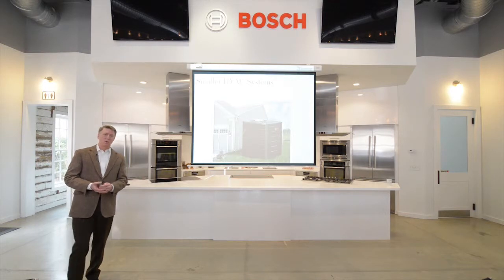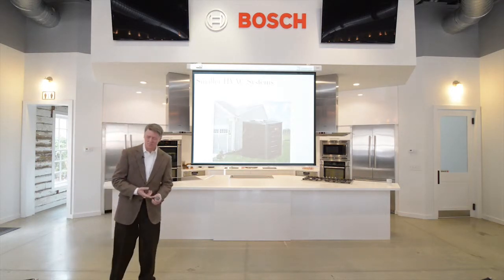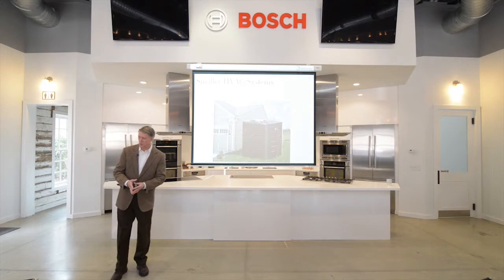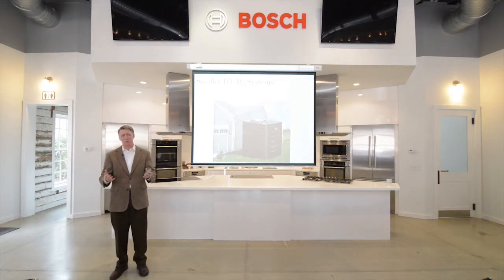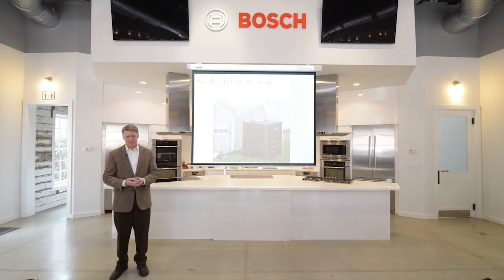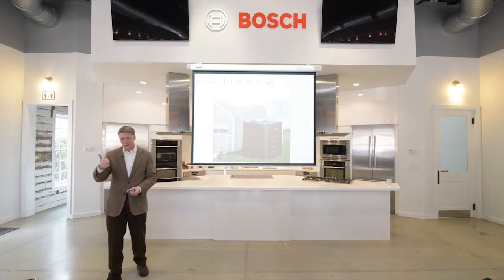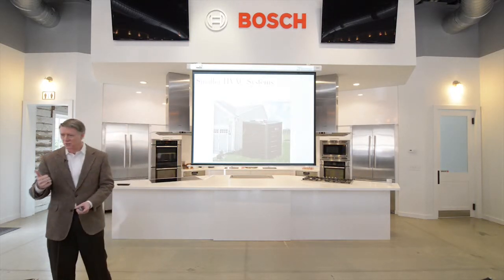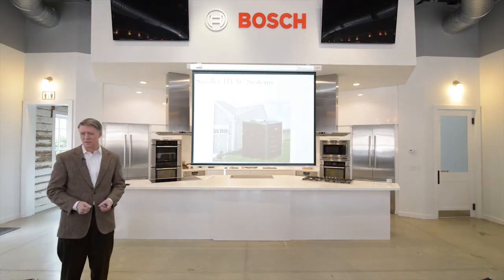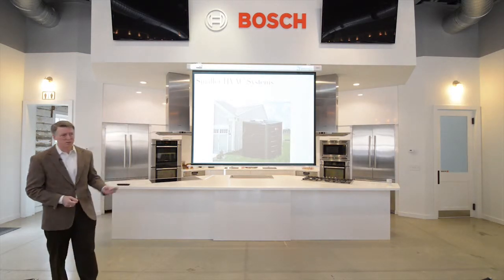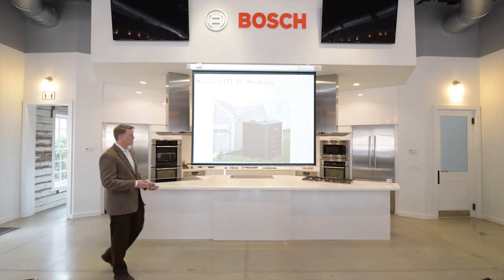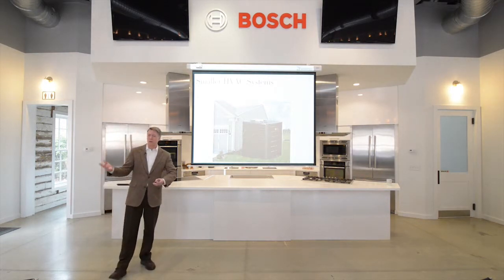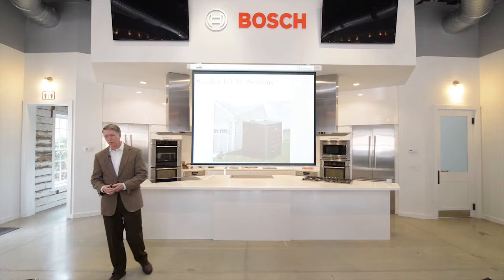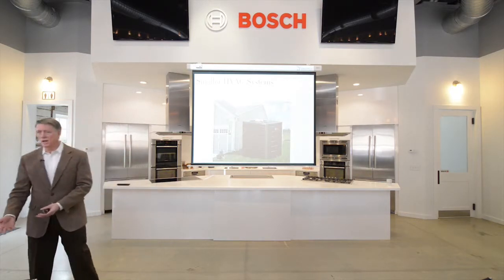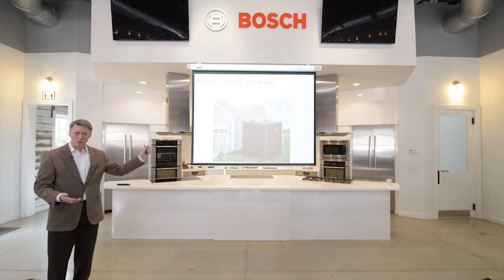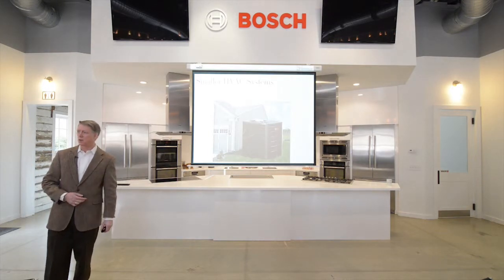And I've seen this on so many houses. The reason is HVAC contractors use rules of thumb. And thumbs are great for a lot of things, but they're not good for designing HVAC systems. You need to use brains for that, and computer software nowadays. The rule of thumb is typically 500 or 600 square feet per ton. So if you got a 2,000 square foot house, your typical HVAC contractor working on a rule of thumb is going to say, we need a 4-ton air conditioner in that house.